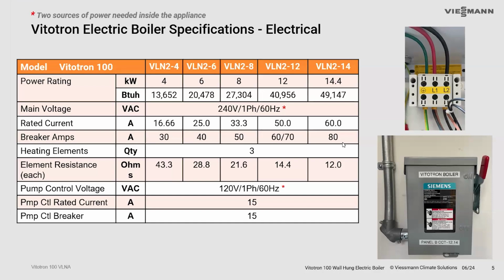We'll have a look at that. There's also, just to mention, a 120 volt requirement, incoming power to operate the pump output. So there are 2 different power sources required. One is for the heating of the heat exchanger, the other is for the pump operation. As far as your rated current, your amp draws and circuit breakers, you can see we go from about a 30 amp breaker on the 4 kilowatt up to an 80 amp breaker on the 14 kilowatt boiler, with a split on the 12 between a 60 and 70 amp breaker. All of them have 3 elements in these units. And of course, the pump output is 120 volt single phase with a 15 amp circuit breaker recommended.